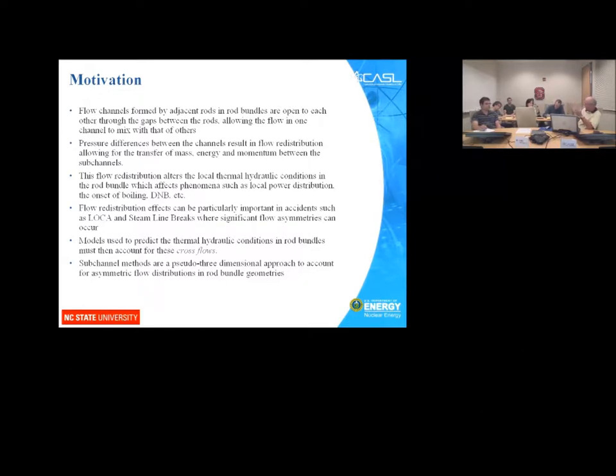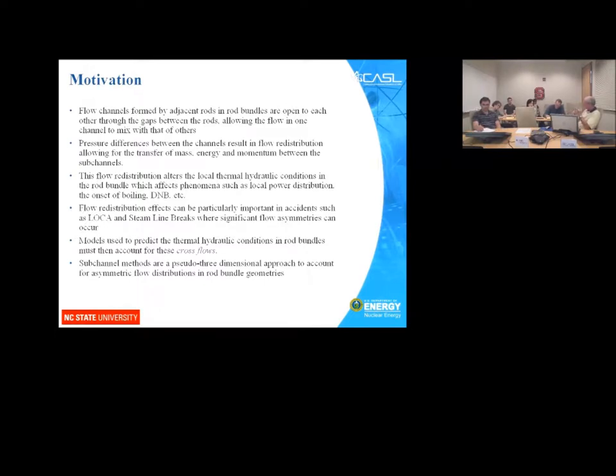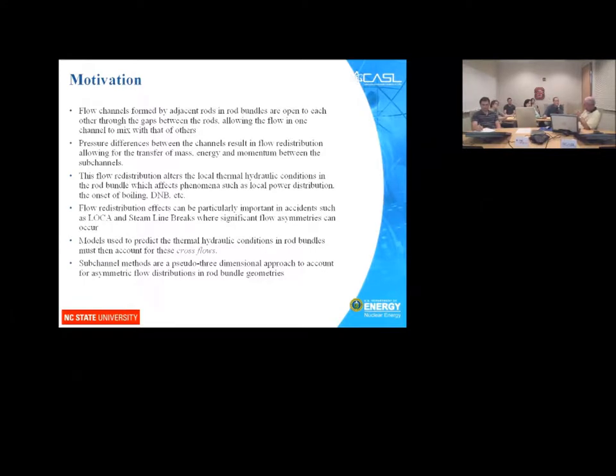A sub-channel is simply the flow channel that exists between — surrounded by — rods. I'll use 'channel' and 'sub-channel' interchangeably. If you have this flow redistribution, fluid moving from one sub-channel to another, it alters the local thermohydraulic conditions: it changes the density, which is important for neutronics calculations because it affects moderation. If you have boiling, that produces void, and the void distribution also changes neutron moderation, reactivity, and radiation transport calculations.